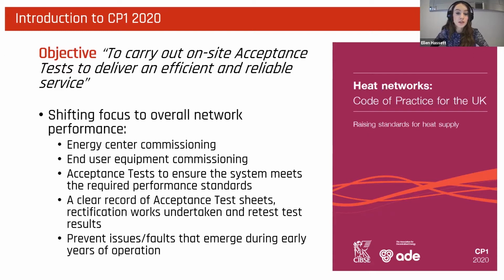Poor commissioning and performance of endpoints, such as heat interface units or fan coil units, is often associated with elevated flow rates and return temperatures, where a few poorly performing units can have a detrimental effect on the heat network's performance and efficiency. Acceptance testing provides performance verification of the energy centre and all the endpoints, which Freddie and I will delve into further. Feedback is then provided to contractors for rectification.